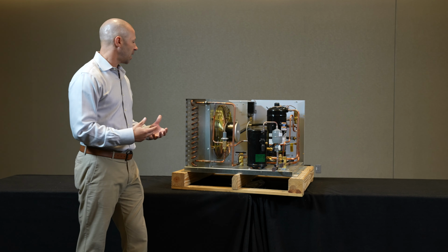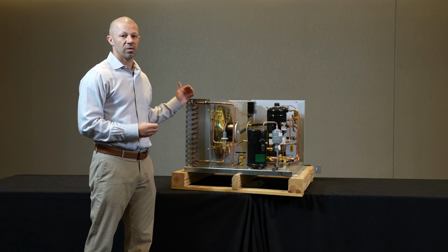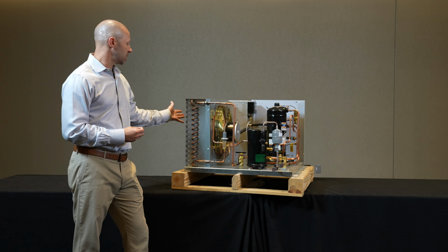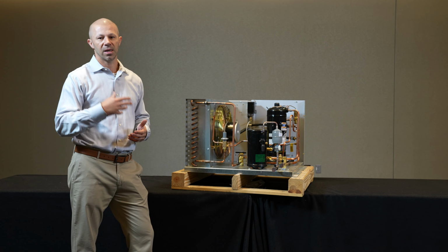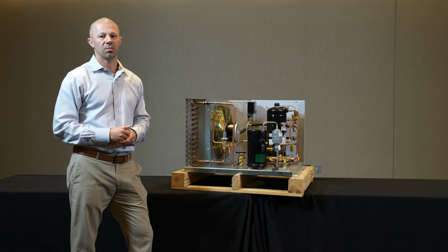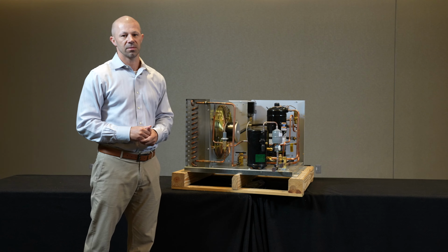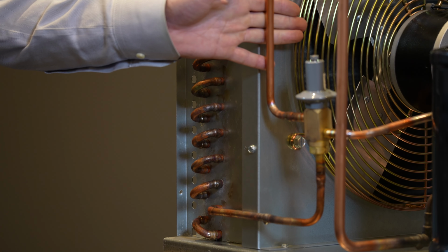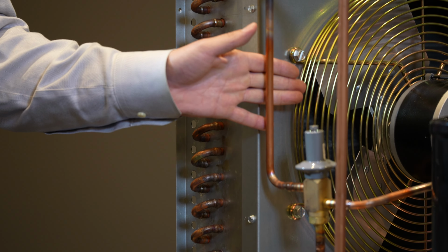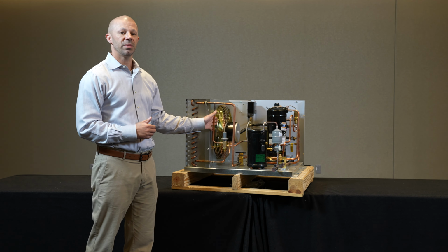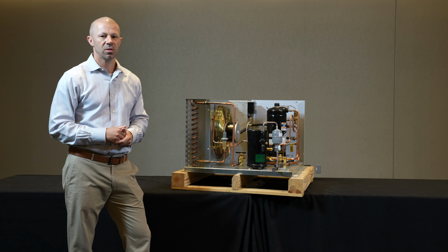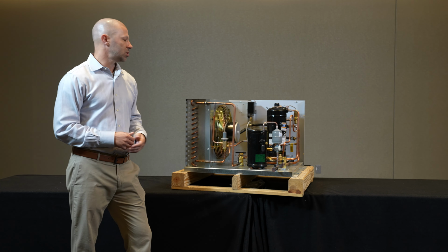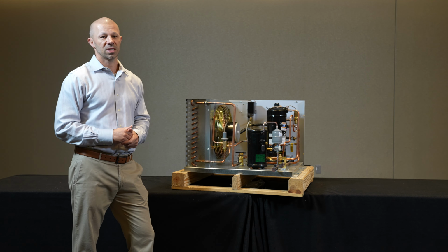It's accepting a high pressure, high temperature refrigerant vapor and cooling that by exposing it to the cooling medium and turning that vapor into a subcooled liquid that will feed our system. One thing on the air side of it is when we are in refrigeration mode, we want this fan motor running full speed, removing as much heat as possible. But as ambients change, we have a level of air side control to go with our head pressure control we discussed in a different video.